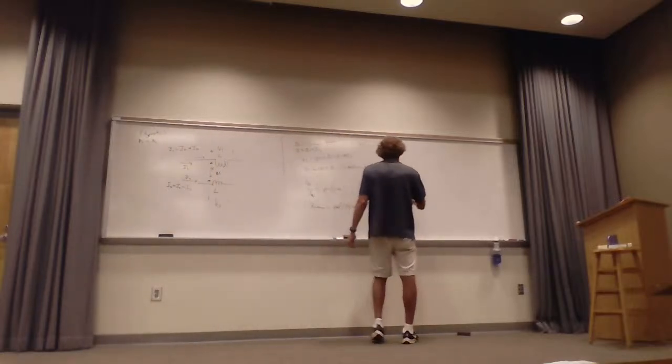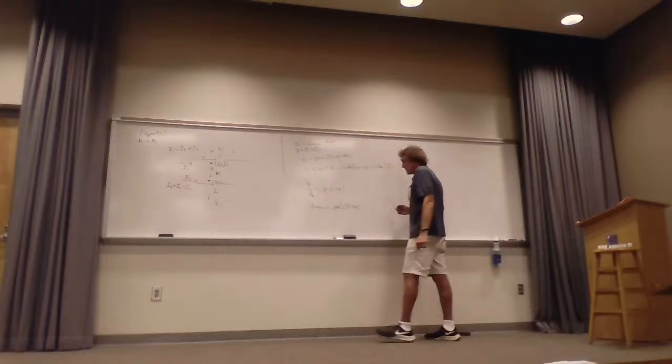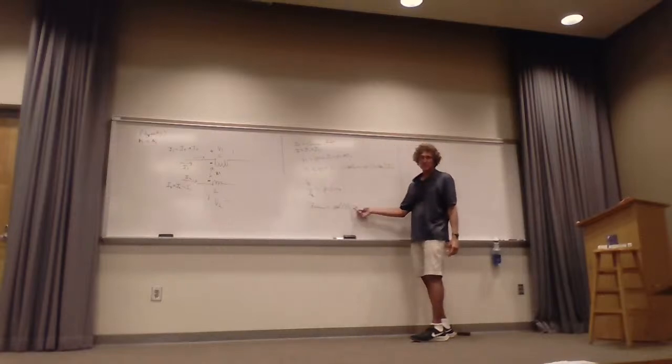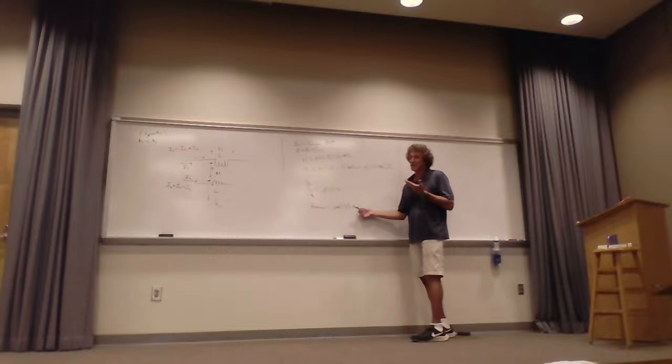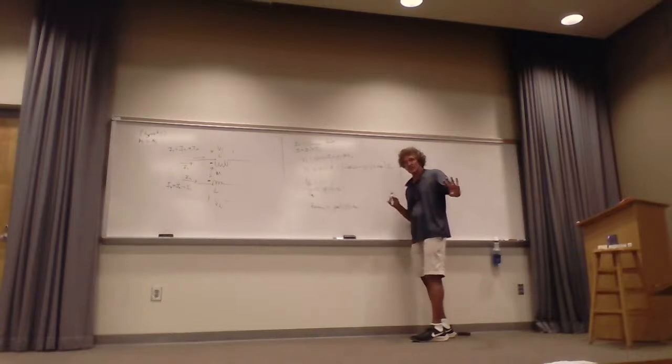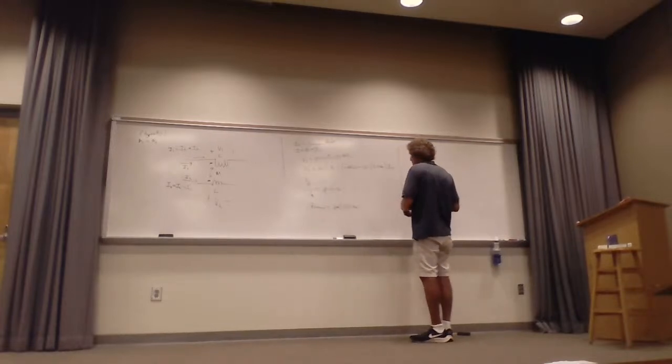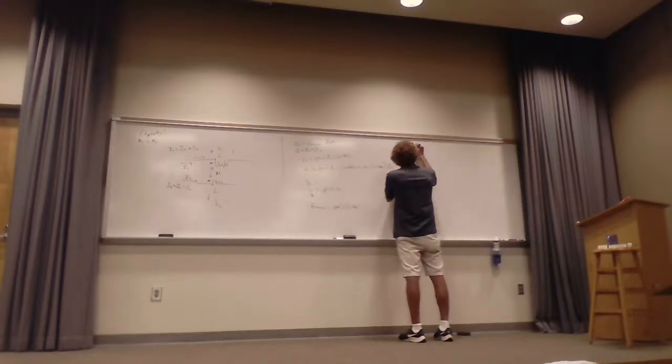Now let's take a look at the effects on differential mode. This is the critical one, because I can make this thing fairly large. And the omega, what I haven't said is when you do common mode currents for transients like lightning, it's not at one frequency. You take a standard current waveform transient, you turn it into a Fourier series, and then you use this as the impedance and get the current. And I don't want to go there now because that's a little too far afield. But y'all follow me on this? Now we come over here and now we do the effect on the differential mode.